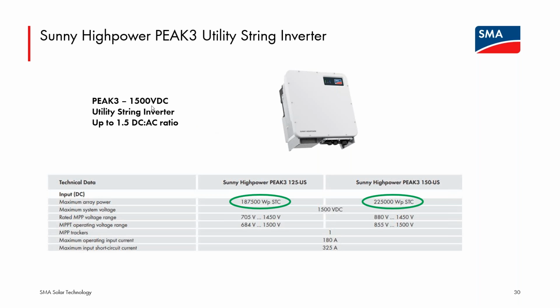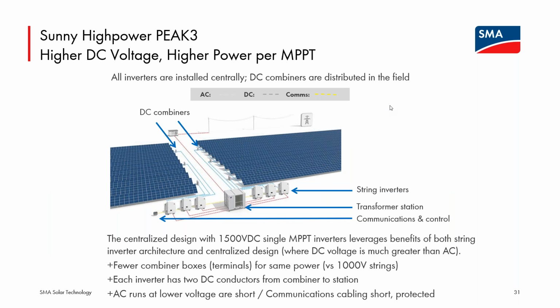In the US, 1500 volts is not allowed on rooftops. It's my understanding that it may be allowed up in Canada on rooftops. This is not intended to be a device used with rooftop arrays. There is no AFCI in this device, and there is no rapid shutdown transmitter. So again, this was intended for large-scale ground mount systems that did not have to comply with those rooftop operation requirements. So apologies if a 1500 volt string inverter with a 600 volt three-phase AC output looks very attractive for certain rooftop applications. That is not what this device is intended for.